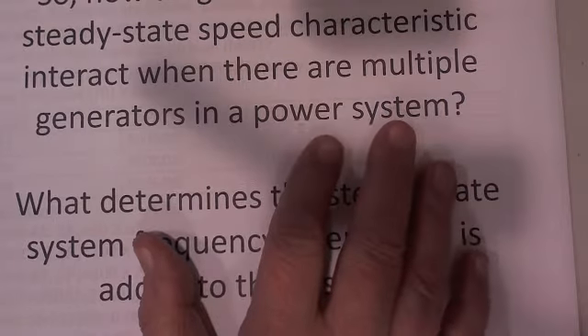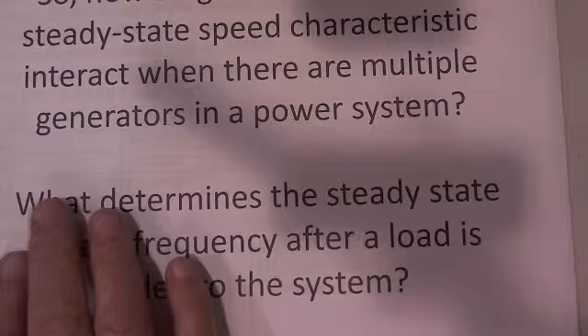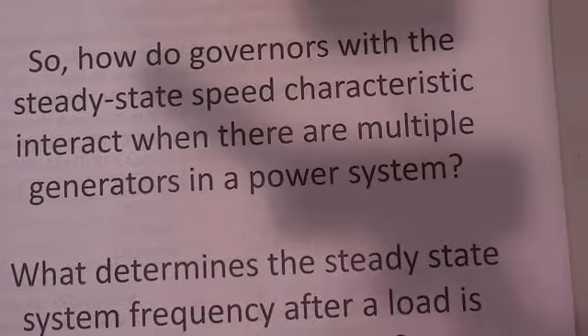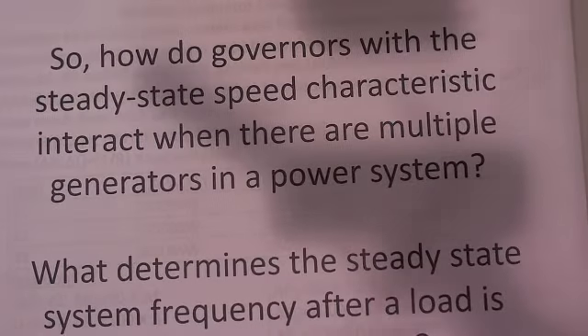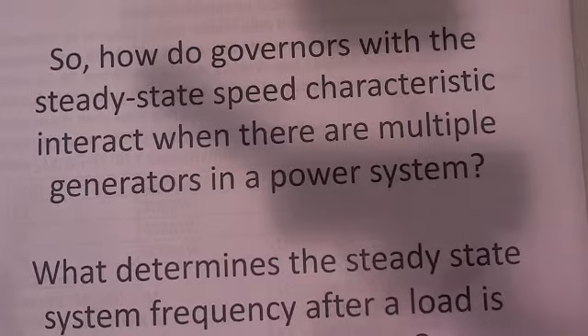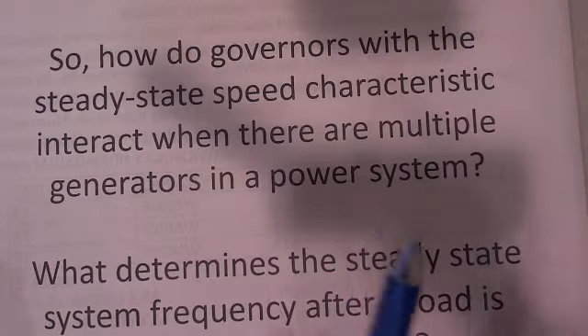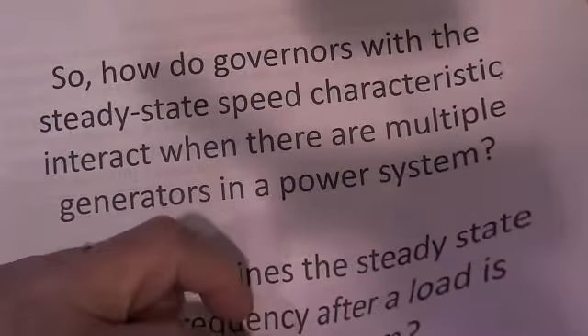So how do governors with the steady state speed characteristic interact when there are multiple generators in a power system? This is what's very, very important. It's very important. And what determines the steady state frequency of the system? How do we get that to go to where we want, to 60?